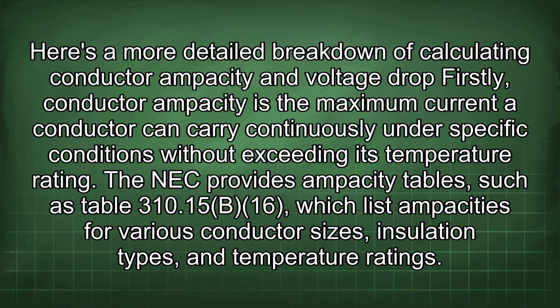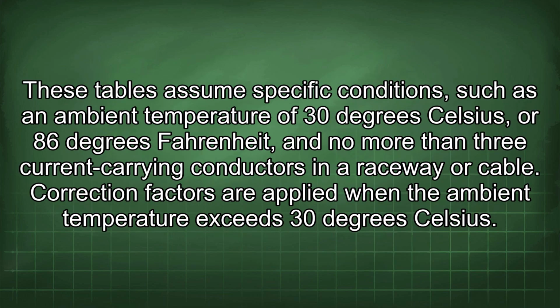Here's a more detailed breakdown of calculating conductor ampacity and voltage drop. Firstly, conductor ampacity is the maximum current a conductor can carry continuously under specific conditions without exceeding its temperature rating. The NEC provides ampacity tables such as Table 310.15(B)(16), which list ampacities for various conductor sizes, insulation types, and temperature ratings. These tables assume specific conditions such as an ambient temperature of 30 degrees Celsius or 86 degrees Fahrenheit and no more than 3 current-carrying conductors in a raceway or cable.